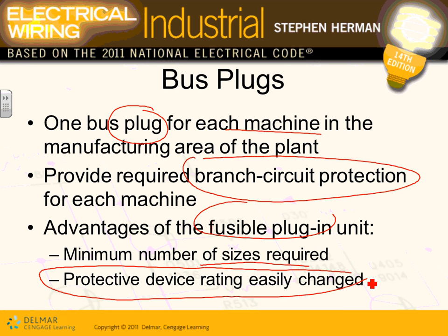If the machine moves from this location into this location, like we were talking yesterday, disconnect the machine, unplug from this, go right here, and plug it right here, and you're in there. I thought they said that it was easy with the feeder too to do that. Yeah, there's a lot of feeders. Feeders will take longer because there's a lot of termination. But the plug-in, you don't even touch a wire. You go untorque them, it's tightened.